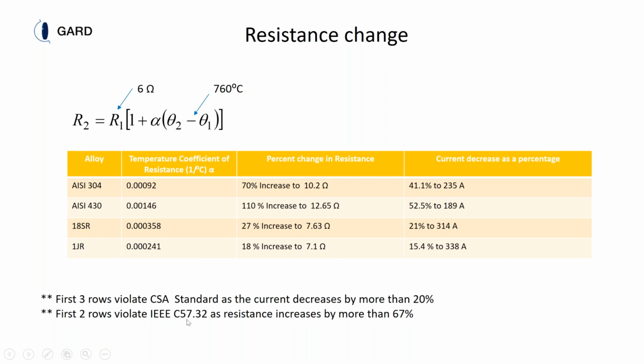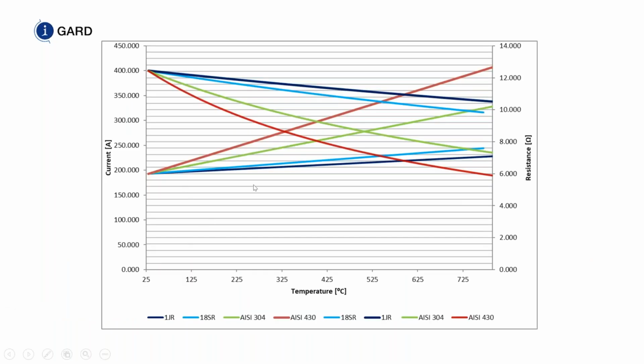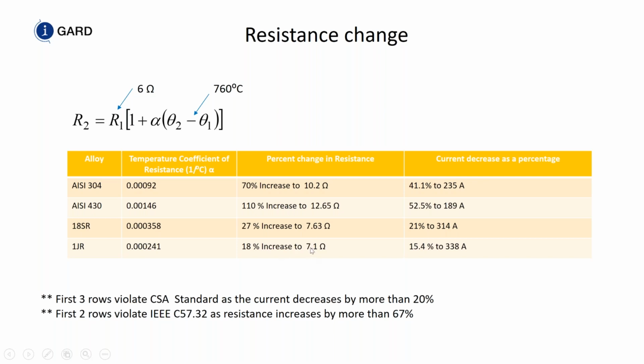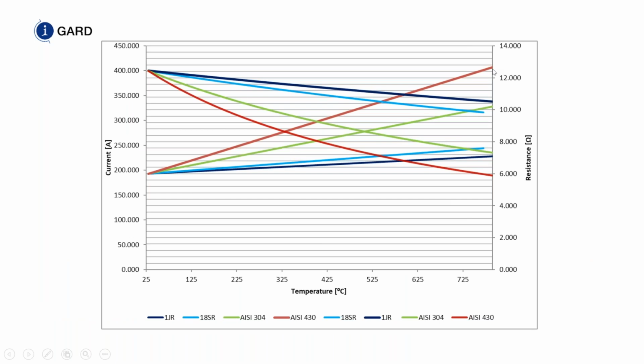And the first two rows violate C57.32 because the resistance increases by more than 67%. This one more than doubles the 430. So imagine if you start with a higher elevated temperature, you're not going to get the current you want to activate your overcurrent protective devices. And this is what this looks like pictorially or graphically. 6 ohms increases to 7.1. But 6 ohms goes above 12 ohms for 430. And we start at 400 amps and we're down below 200 amps at the end of 10 seconds.